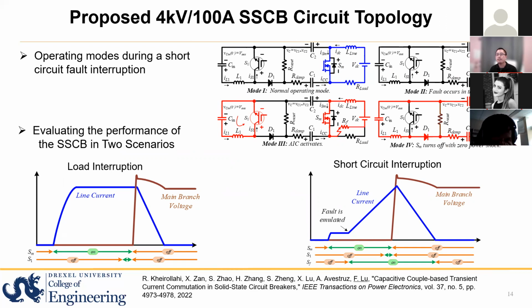In the second mode, let's say we have a short circuit. If we have a short circuit, there's a huge current increase in this loop, and then we turn on our auxiliary circuit. This auxiliary circuit will generate a reverse current. At first we have this additional switch to generate a current, and once the current magnitude is large enough, we turn this off.